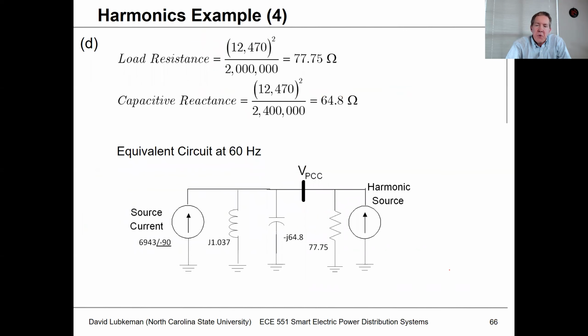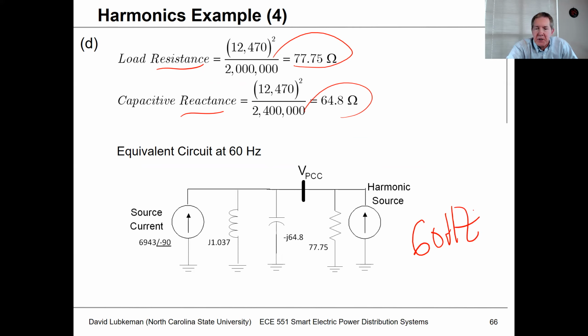Now, if you wanted to see what the impact at different frequencies is on the voltage, then I can calculate an equivalent resistance and reactance. The way I do this, if I take V squared over P, this is going to give me the equivalent resistance. If I take V squared over Q, this is going to give me the equivalent inductive resistance, or reactance, I should say. And so what I have here at 60 hertz, the fundamental, is this equivalent circuit. Okay, I can convert this to a Norton equivalent.